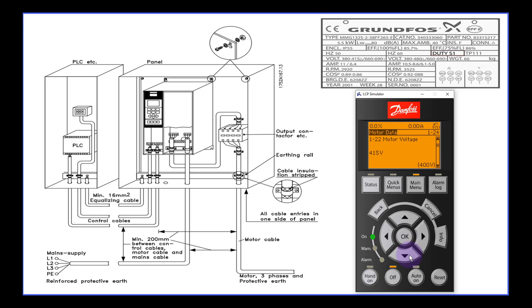Press the down button to go to the next menu — motor frequency. Our country uses 50 Hz, so I will change it to 50 Hz. Press the OK button to edit. Use the left/right arrow key to move to the next digit, and the up/down arrow key to change the value. Press the left arrow key and press the down button to change to 50 Hz, then press OK. Press the down arrow key to move to the next menu.